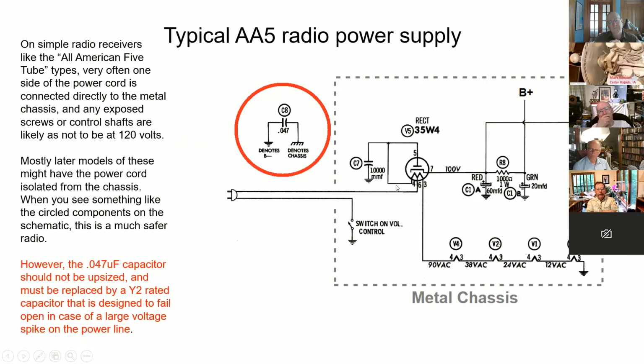But if there is a short circuit between the B minus, which might be hot, you got a 50-50 chance. This will only pass a little bit of current, very little, maybe a few milliamps at 60 hertz. And so you might get a little zap or tingle off of the chassis if something like that happens, but it's not going to be the same as if you just tied this straight to the metal chassis, if that makes any sense.